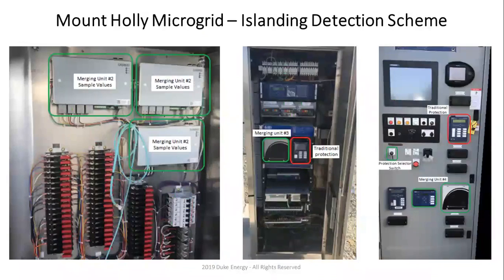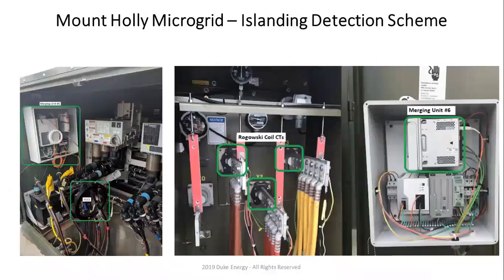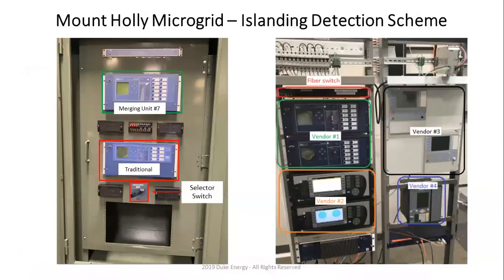In the middle, you see the grounding transformer that has traditional protection and merging unit 3. On the right side, you see a generator. Again, everything has a traditional protection as well as the merging unit. We also have a selector switch, so we can switch between the two. You can also see on the left side the fiber optic current sensor that we are testing. That itself has its own merging unit. We have some Rogowski coils on the low side of the transformer that have RJ45 as output. These are the new CTs that we're testing. You can also see what is being built now for the microturbine, another merging unit, and again traditional protection with a selector switch.